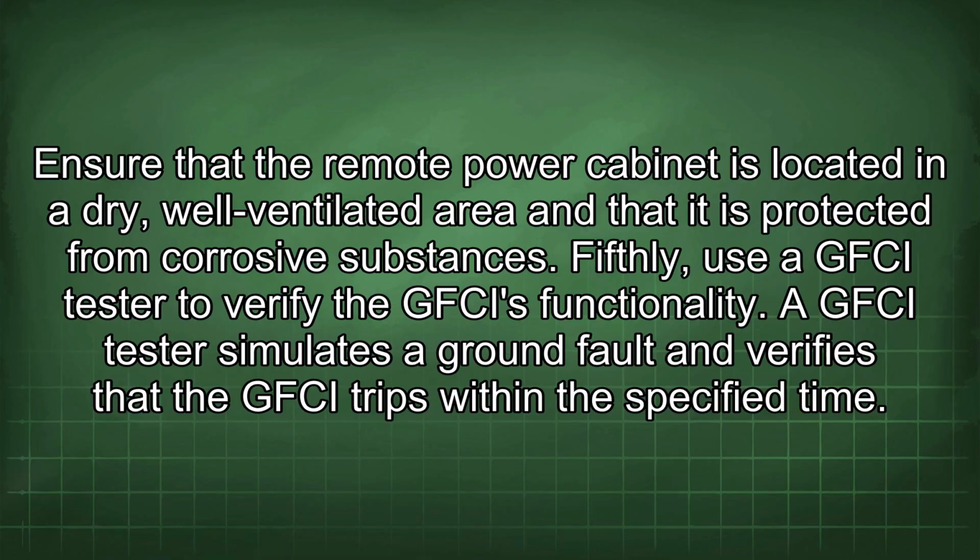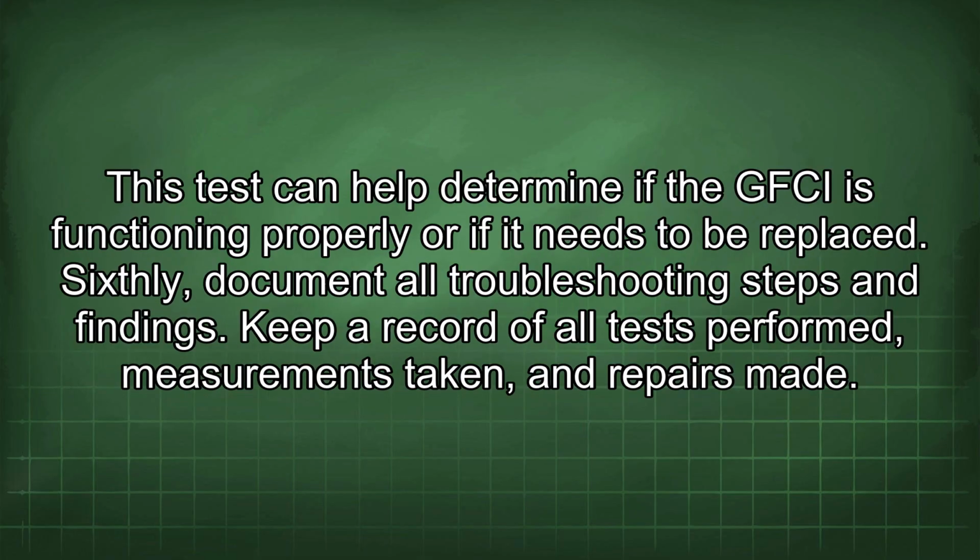Fifthly, use a GFCI tester to verify the GFCI's functionality. A GFCI tester simulates a ground fault and verifies that the GFCI trips within the specified time. This test can help determine if the GFCI is functioning properly or if it needs to be replaced.